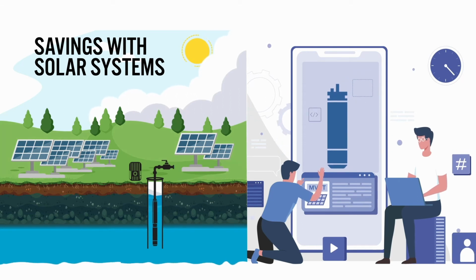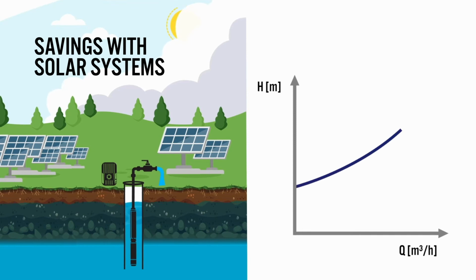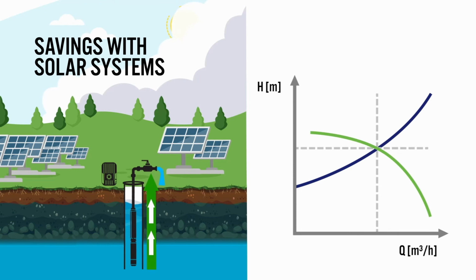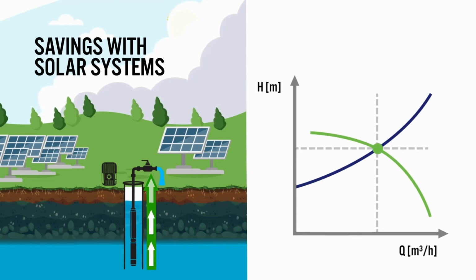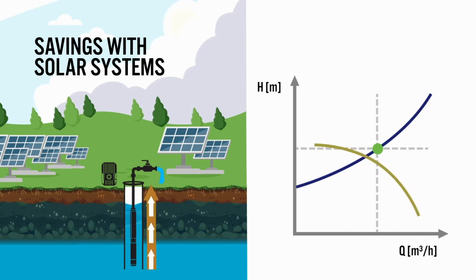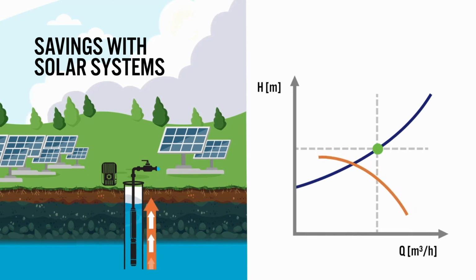Even more important than the electrical power is the sufficient voltage. The connection of sufficient solar panels in series will generate the voltage level needed to operate at full speed. But if weather conditions change, the voltage can drop, causing the system to reduce pump speed to keep running. This reduces the amount of water pumped, but not just linearly. Due to pump affinity laws, the pump head or pressure is reduced squared, which then leads to a further reduction in water flow as you run at a different pump operating point.